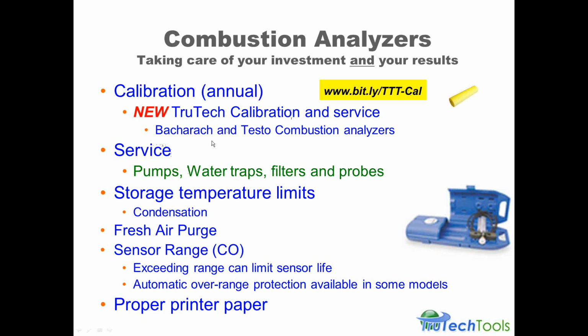So there are some other service factors or points of service, things like the pump that pumps the flue gas through, the water traps, filters, and probes. You want to make sure those are all in proper working condition, and those things are examined during the calibration service that you'd get from basically anyone that does service on analyzers.